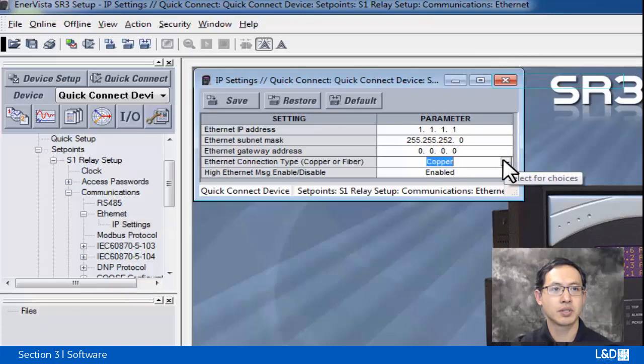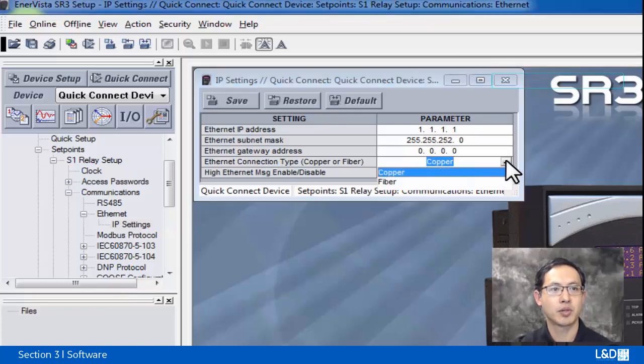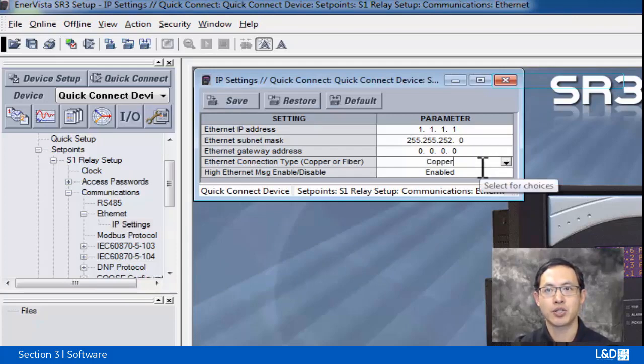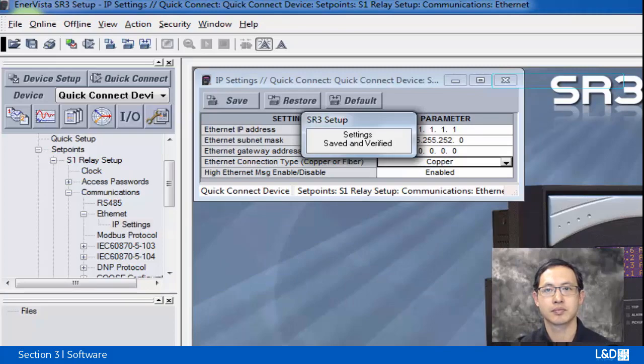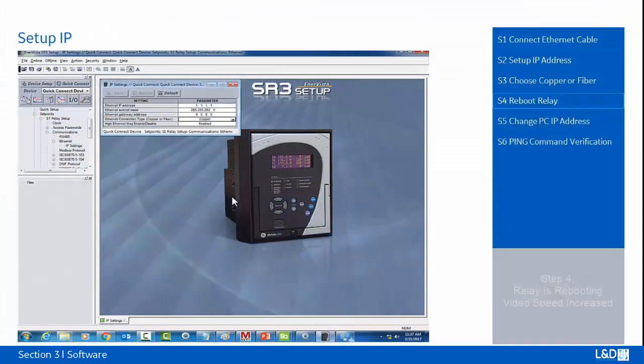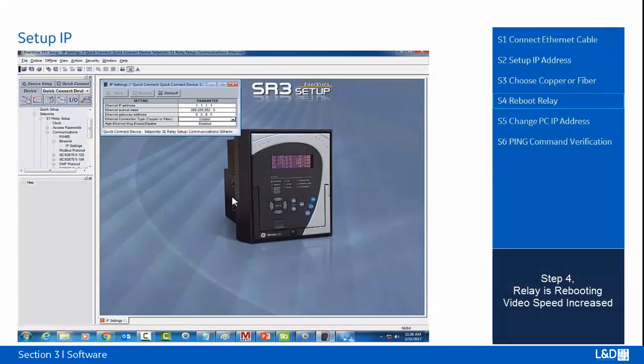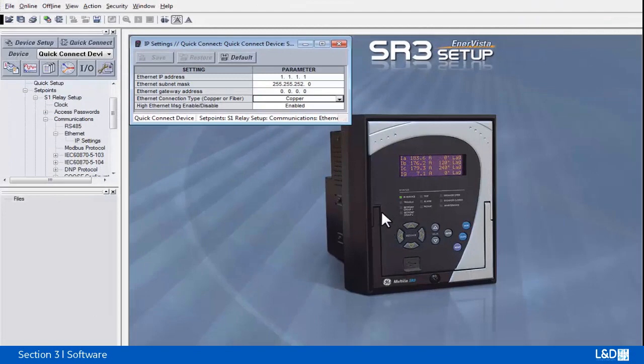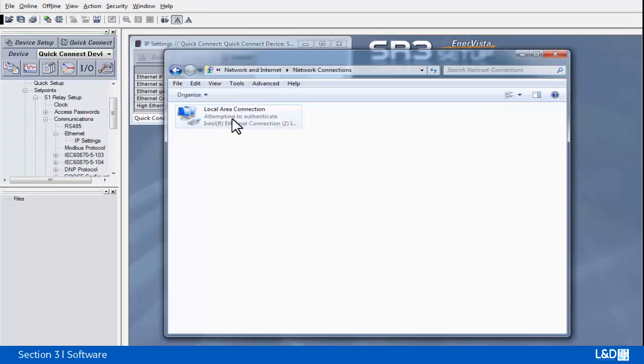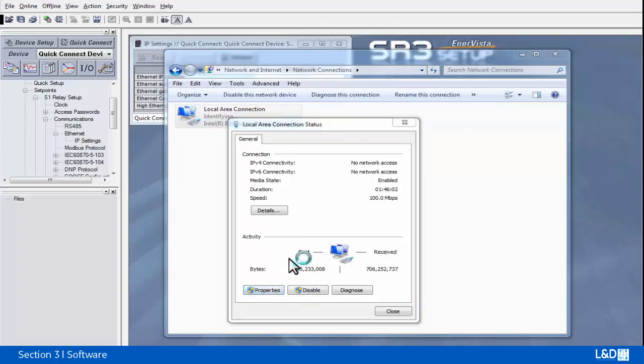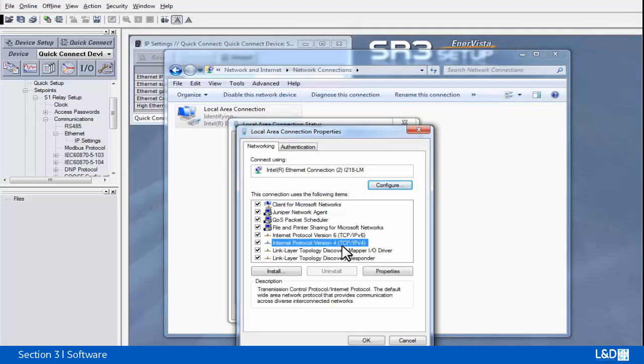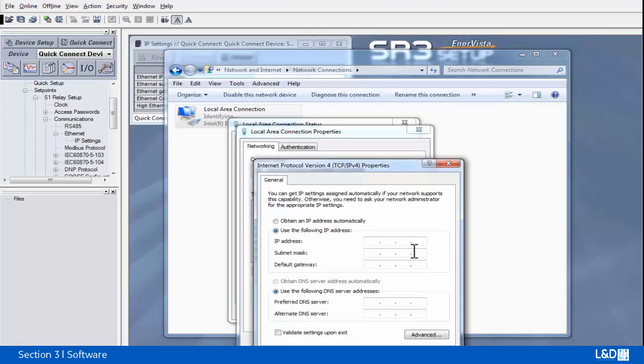Step 3 is important, depending on what type of connection. You can choose copper or fiber. Since we're using the RJ45 port, I'm going to choose copper, but you can also choose the fiber optical cable for this Ethernet connection. And then we need to click Save. Then step 4, and step 5 is to change the PC local area connection address. So we can start the local network adapter settings and change the properties. Choose TCP/IP v4 and enter a different IP address.